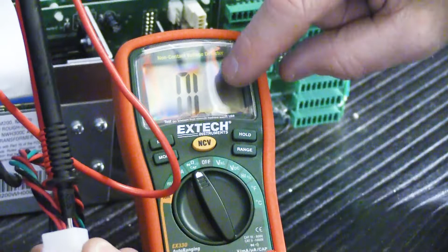Now this is my master station, not Rocky's master station. But the idea is, if he caused some kind of severe damage to his NM100 and there's a short in the master station, either on one set of power inputs or the other, when you put the probes into the plug-in, if there's a short, it's going to show continuity, because continuity is a closure, is a short, and it's going to show some kind of resistance. What kind of resistance is it going to show? I don't have any idea, because it depends on what happened to it.